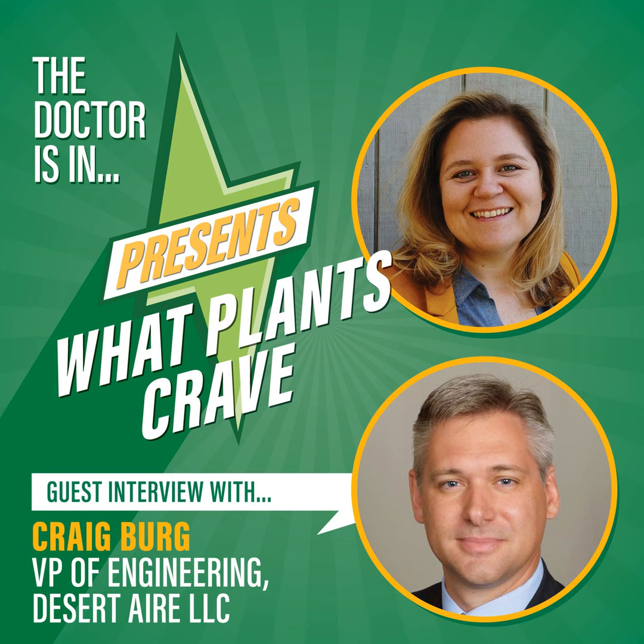Absolutely. This is the livelihood for a lot of growers, so making sure we're keeping ahead of any situations—I'd recommend doing almost a recommissioning on a regular basis, as much as twice a year. Have someone go check the temperatures and pressures again, not just change the filters, but look at how the system is operating, even compare how it was operating last year at the same time, so we can get ahead of any issues before they occur. Every time we take a unit offline unexpectedly, that's costing money and productivity, and delaying us. So keeping up with all these things is very important.